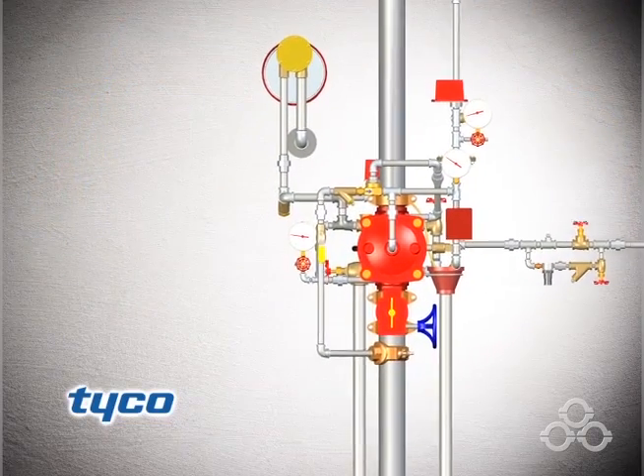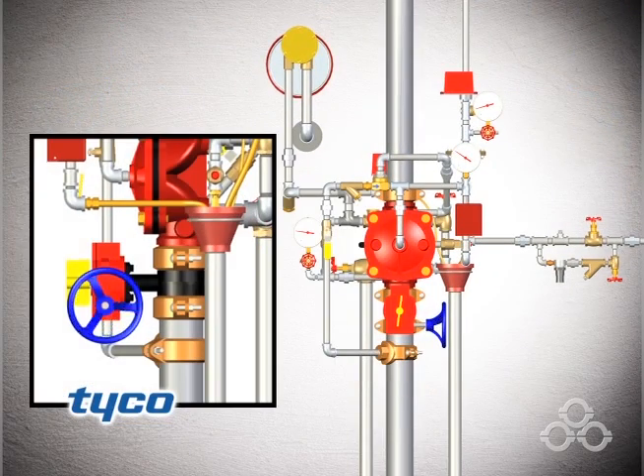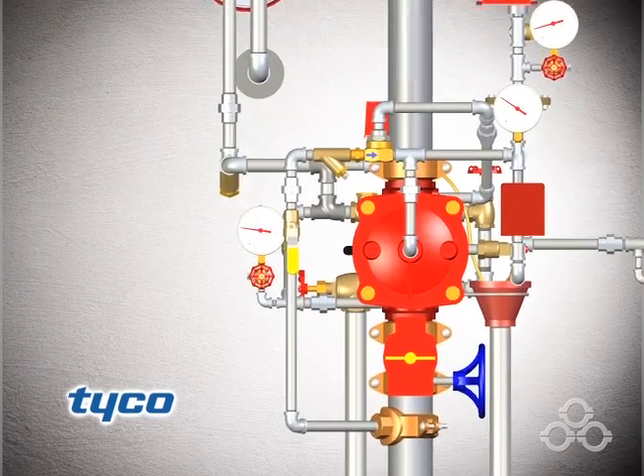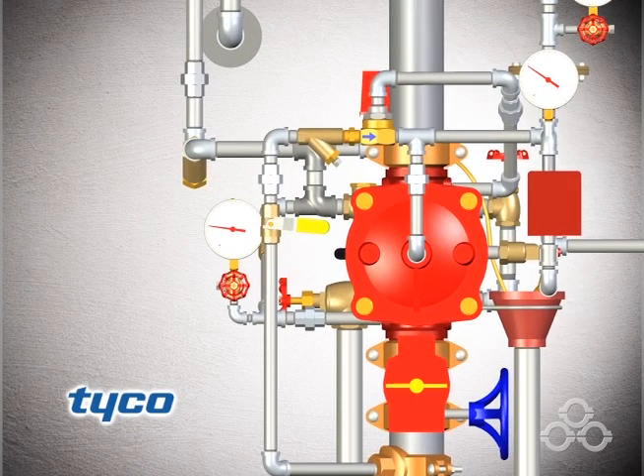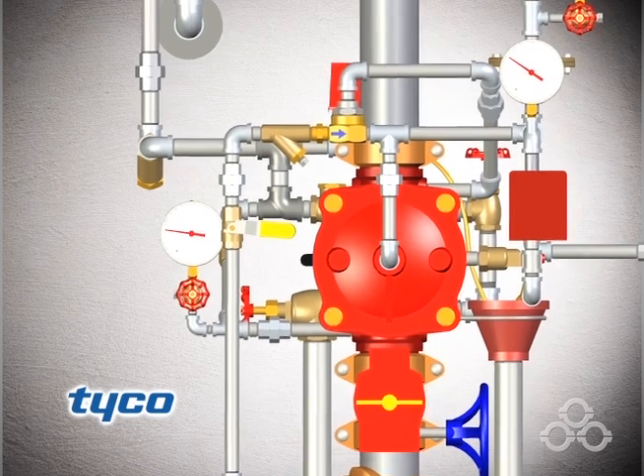To reset the valve after the fire is under control, the main supply control valve is manually closed to shut off the water supply. The diaphragm chamber supply control valve is also closed.